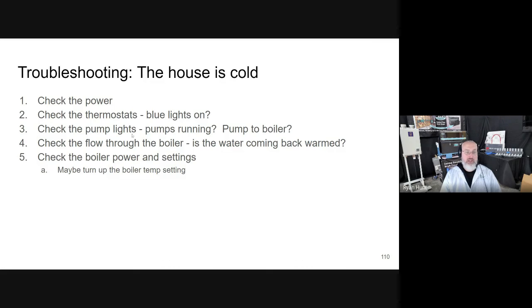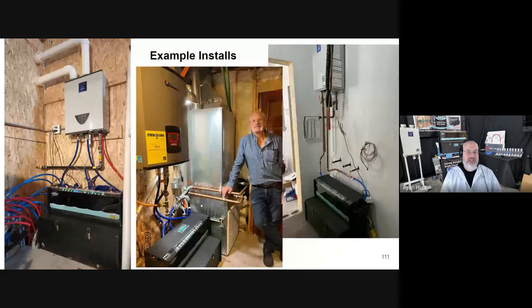Then you check the pump lights. Are the pumps running? Is the pump to the boiler running? And if the pump to the boiler is running, is warm water coming back to the tank? So you check the flow through the boiler. Is the water coming back warmed? If that's not happening, then you check the boiler power and settings, and maybe turn up the boiler temperature setting so it's providing more heat into the tank. That's if everything's just cool as opposed to dead. So that's it in a nutshell.